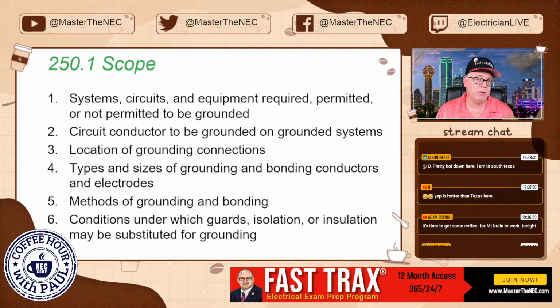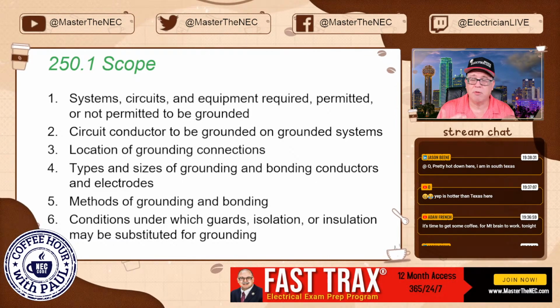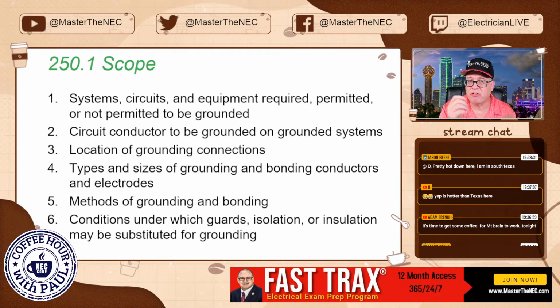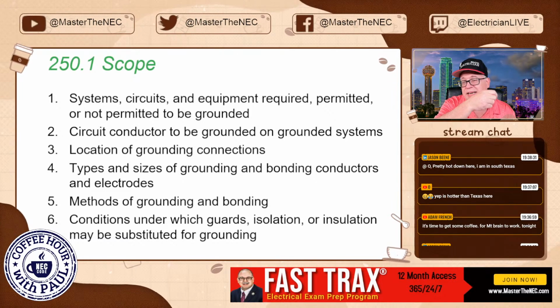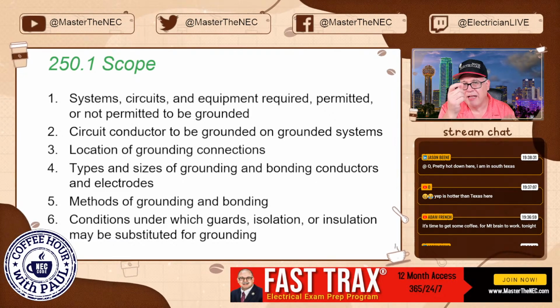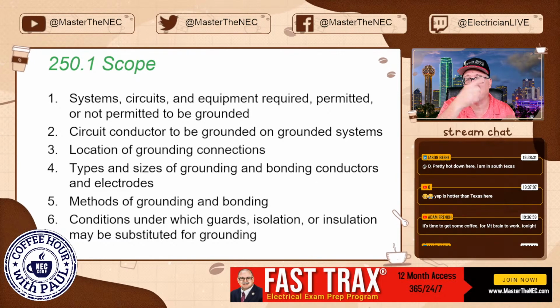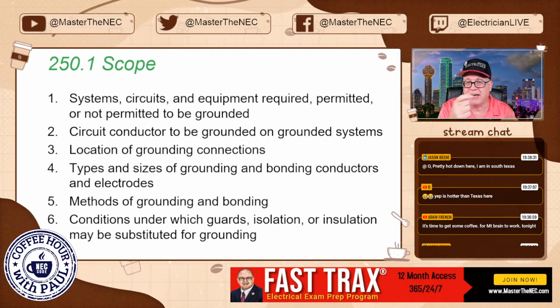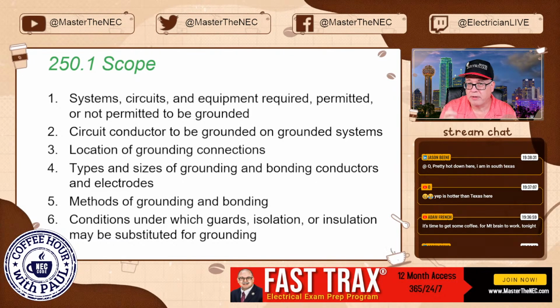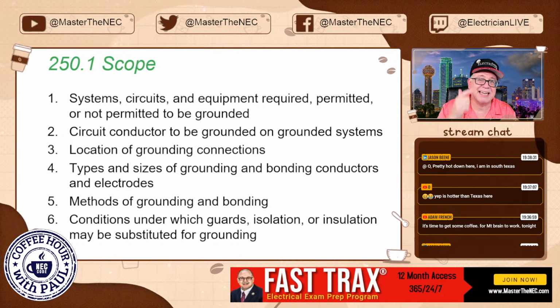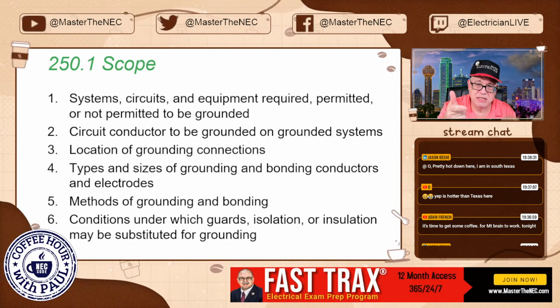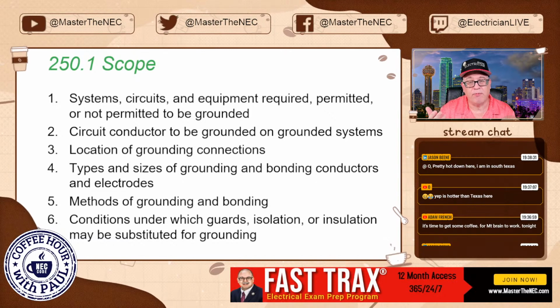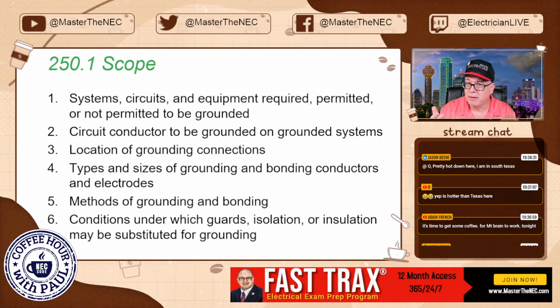The biggest issue in this one was they didn't remove the main bonding jumper, which was up in the service, but now they're doing it to a remote distribution panel. That green screw, which would have been the main bonding jumper back at the service equipment, wasn't removed. And so now the neutral is making contact with the metal case. Now, they did run 4 separate conductors. That's good.